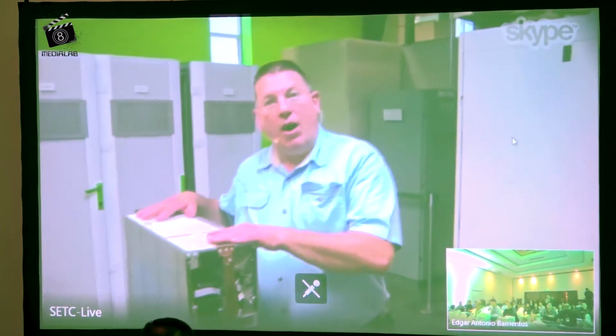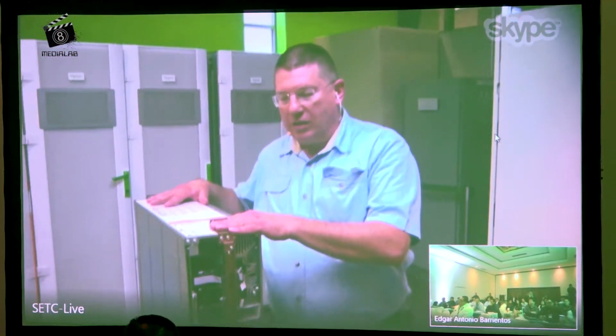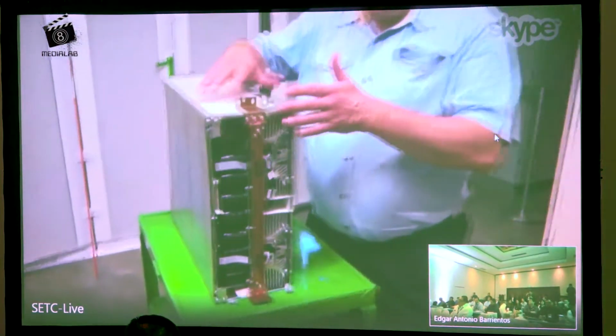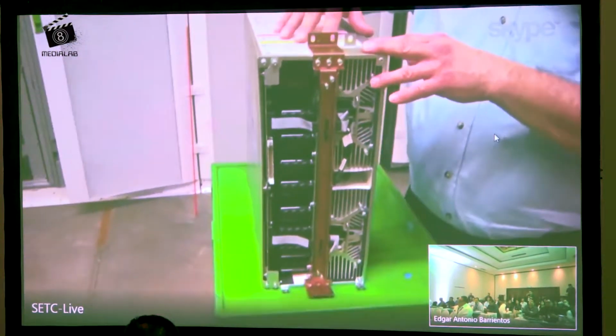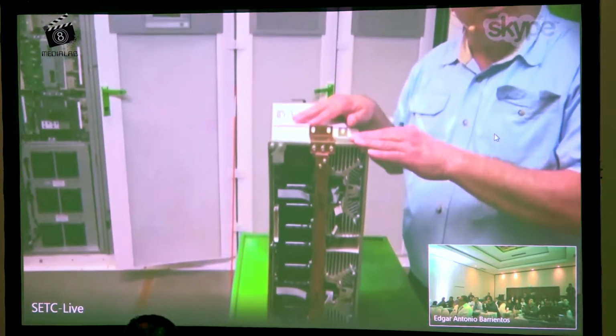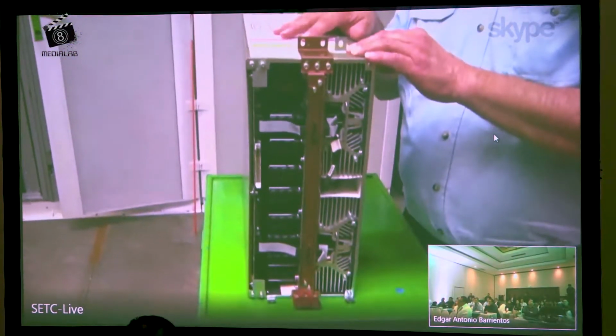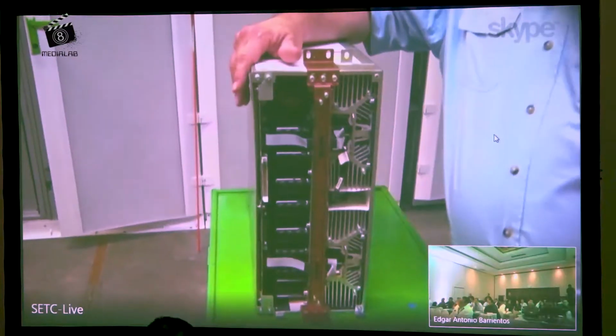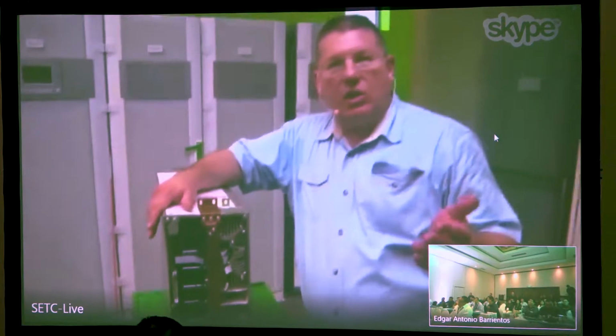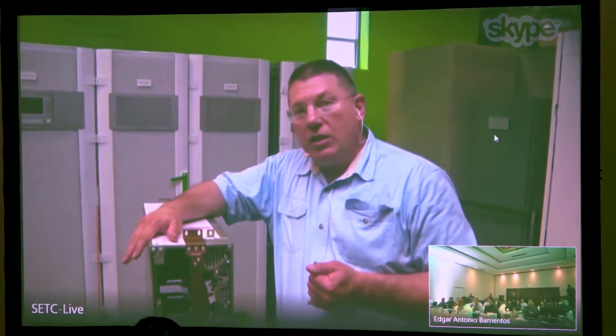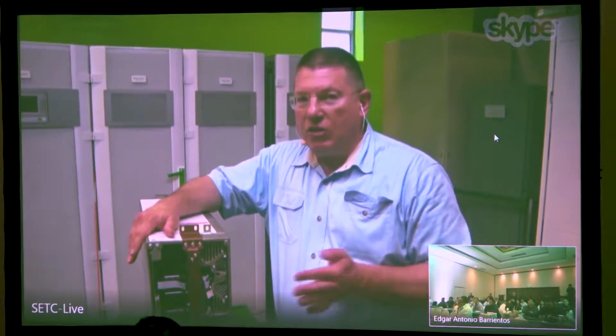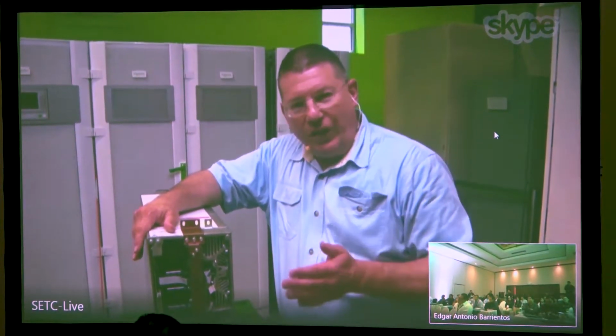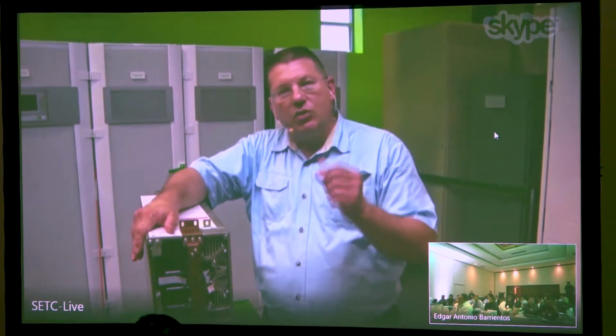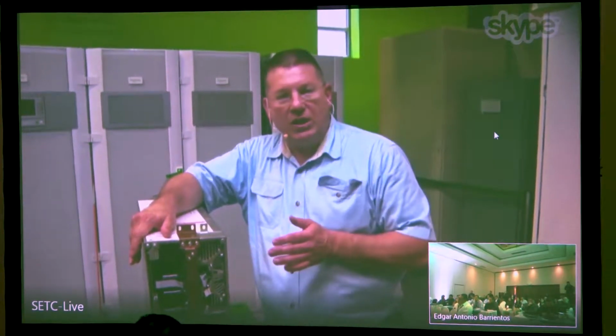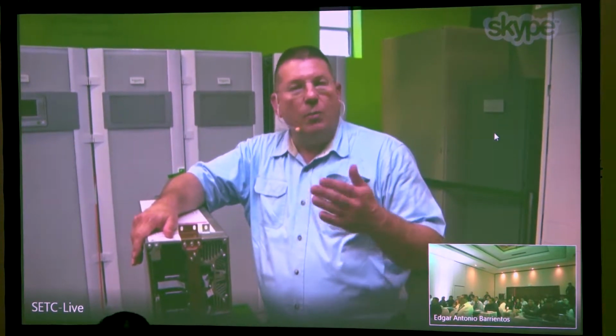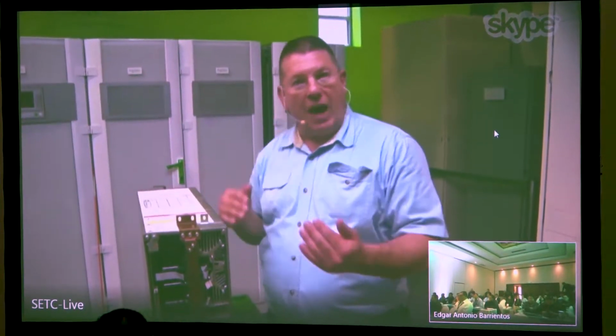So this is a power block for the UPS. And we, Schneider, have developed and deployed a patented 4-level inverter circuit for this UPS. Everybody in the UPS industry is using a 3-level inverter. This is the first, and to my knowledge, the only 4-level inverter in the UPS industry. What is significant about this is that we're able to reduce switching losses across those IGBTs, and that helps us both with efficiency as well as with reliability.